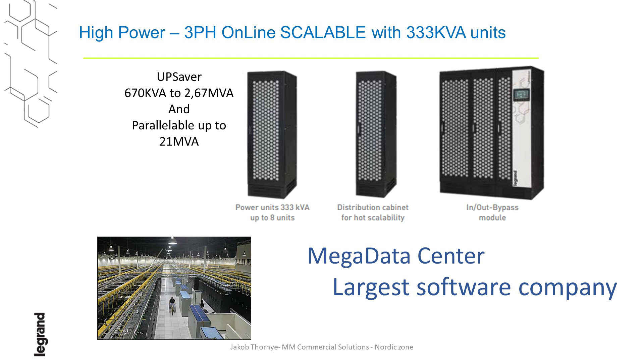Which means that service is very cheap and very easily done. Yes, it has a cost in installing, but it means you can very fast replace everything. Every single battery drawer inside these cabinets weighs no more than 16 kilos, because that means you're allowed to work with them for more than 6 hours according to EU rules. If they weigh 20 kilos, you are not allowed to work with them that long. So the battery drawers, the power modules inside, are based on very fast handling.